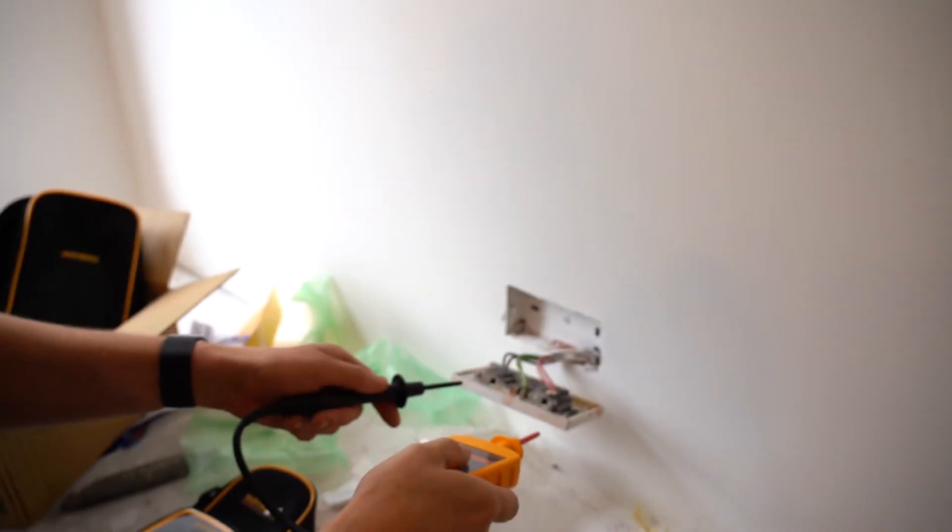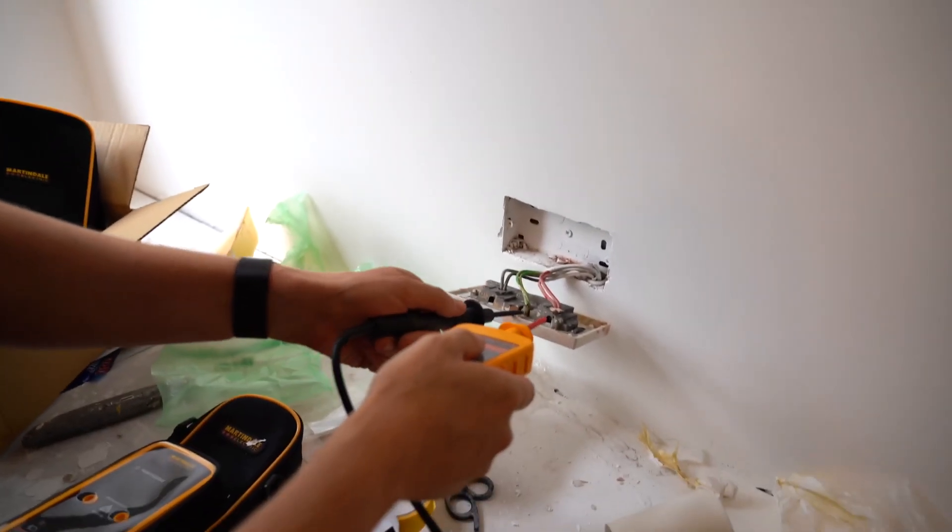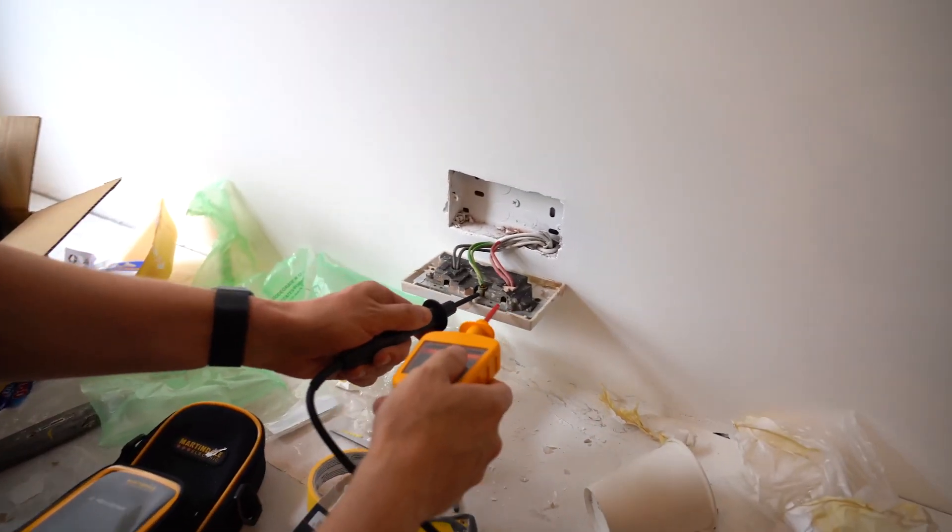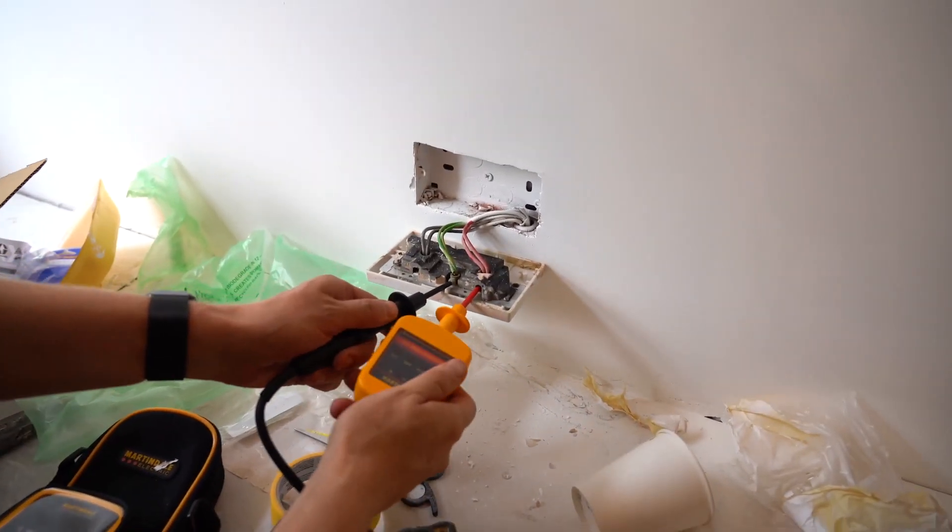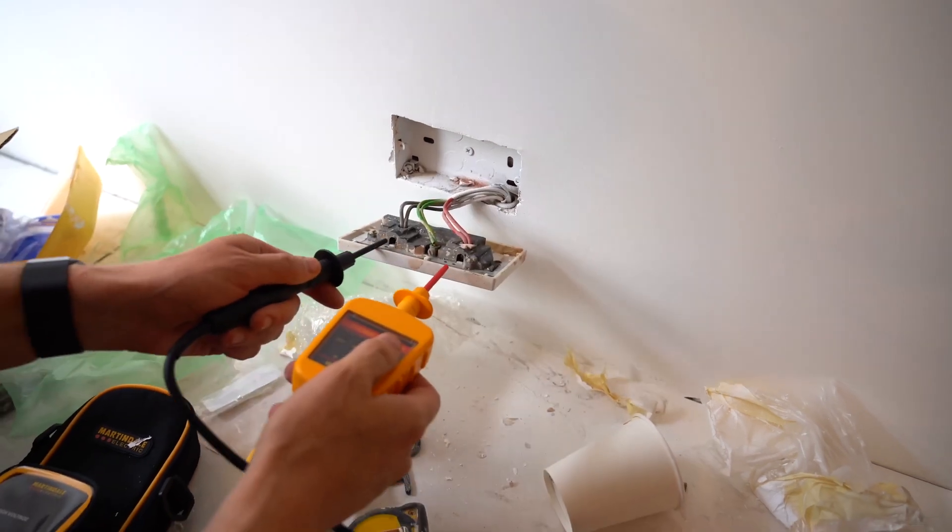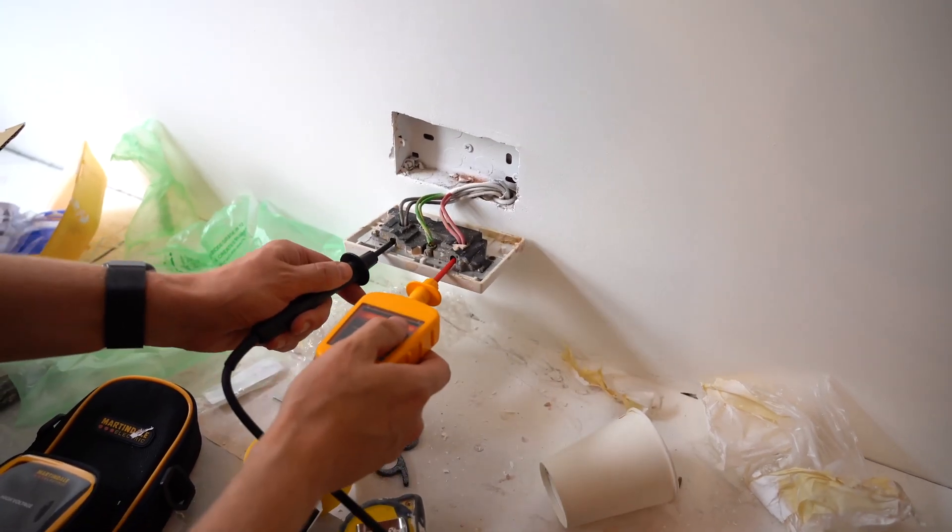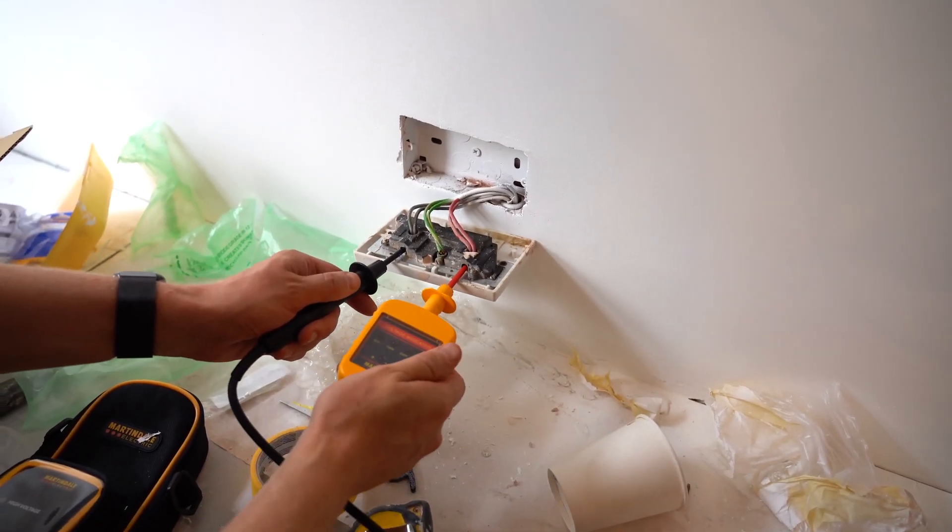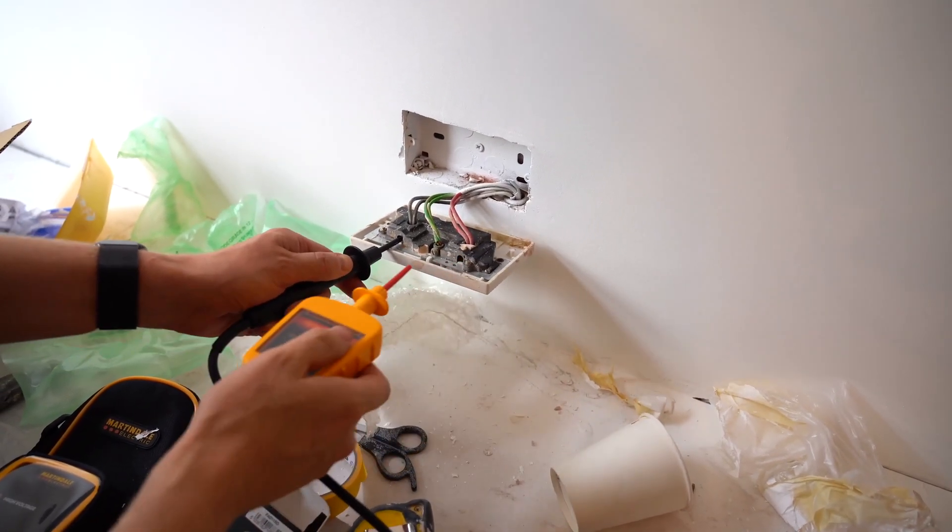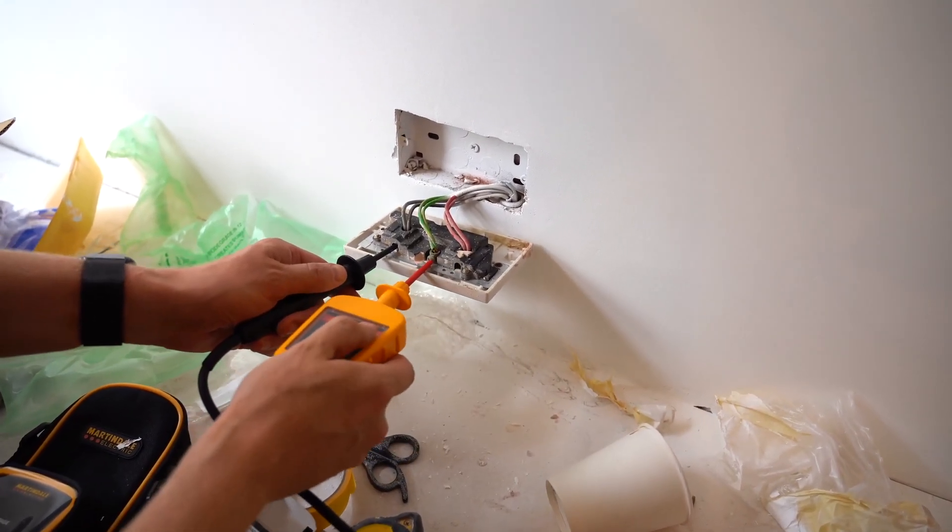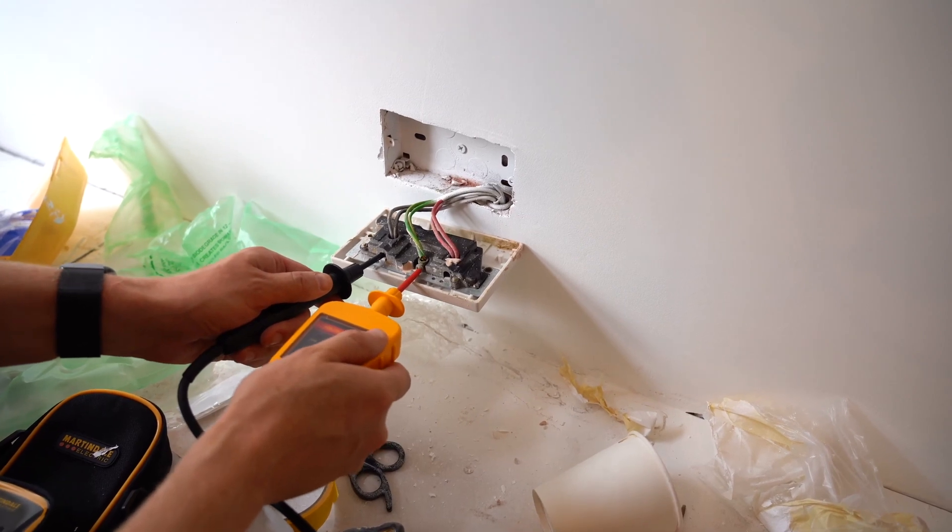So now we're going to test here and we're going to do our various combinations of tests. We'll do CPC to line, so we've got no power. We're going to do neutral to line, no power. Neutral to CPC, no power.